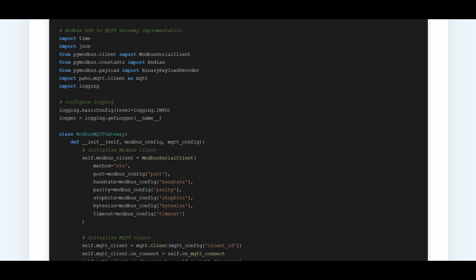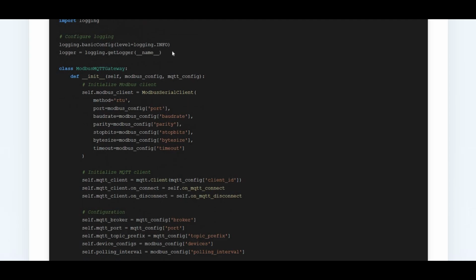On the MQTT side, we use the Paho MQTT client, which is the standard Python client. Logging is added because gateways run unattended. When something breaks at 3 in the morning, logs are what save you. Right after that, logging is configured at info level here. This is a deliberate choice. Debug is too noisy for production, error alone is not enough, and info gives you lifecycle visibility without drowning the system. Then we define the ModbusMQTTGateway class. This is the core abstraction. Everything the gateway does lives here.